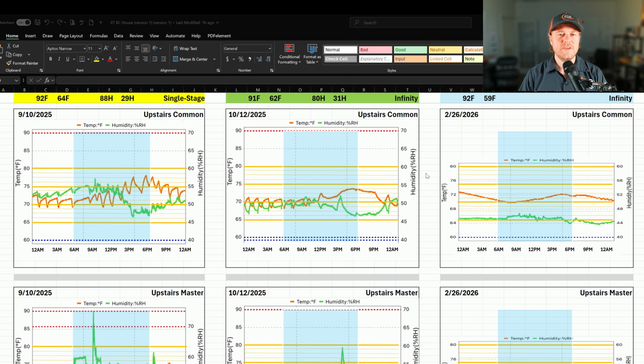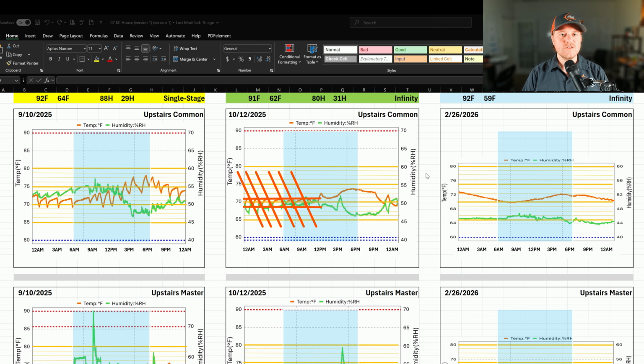Because there's not much of a heat load, it's really interesting to see how this system is running. If we take a look at this graph right here, you can see the temperature swings going up and down by about 2 degrees. And the temperature swings are happening every time that the AC turns on. When we take a look at the other graph, we're not seeing that at all. And at first I thought there was something wrong with the data loggers. But I know that there's no way that 5 different data loggers would all be doing the same thing. So I know that they're working correctly.